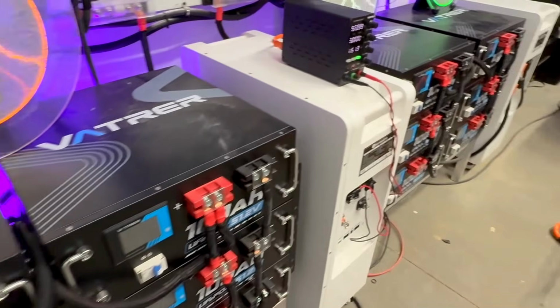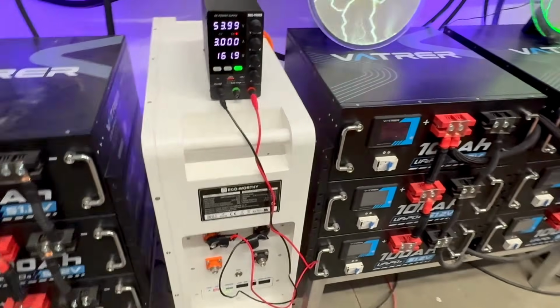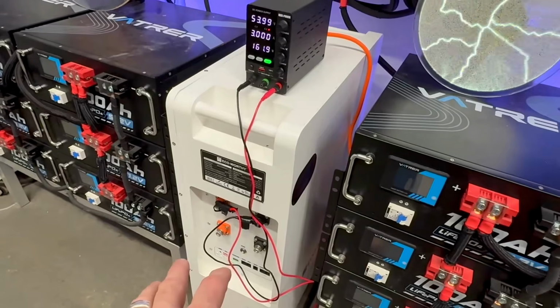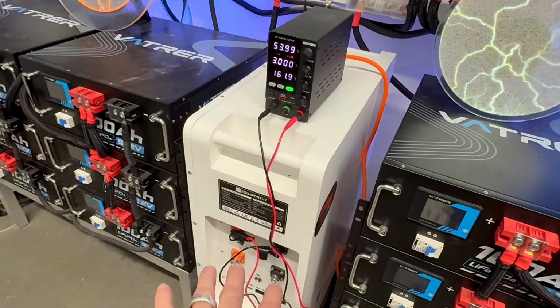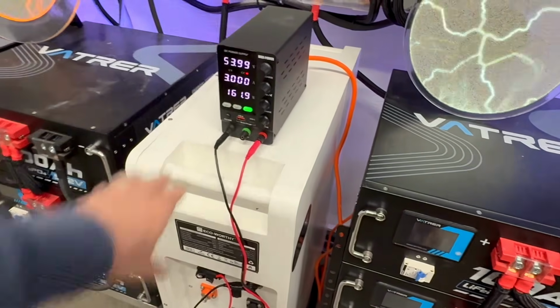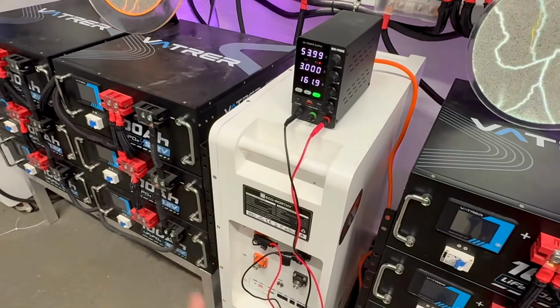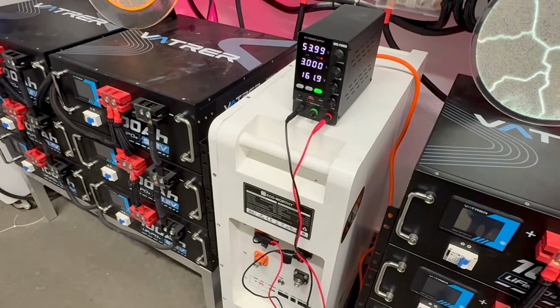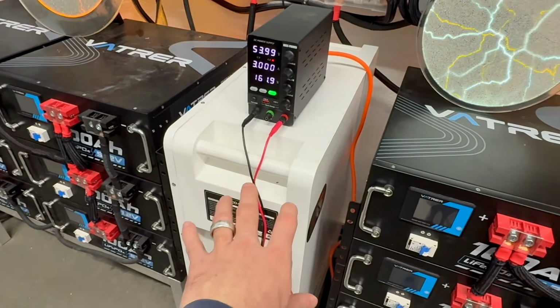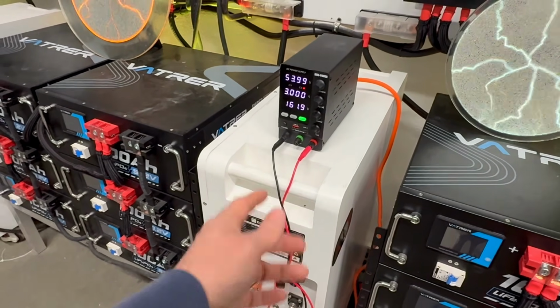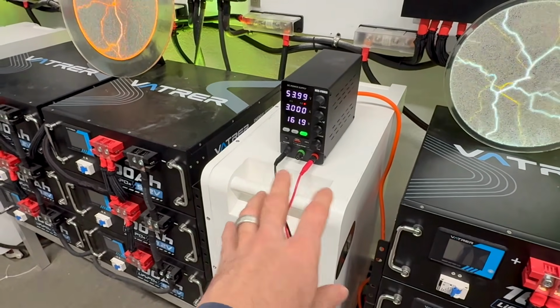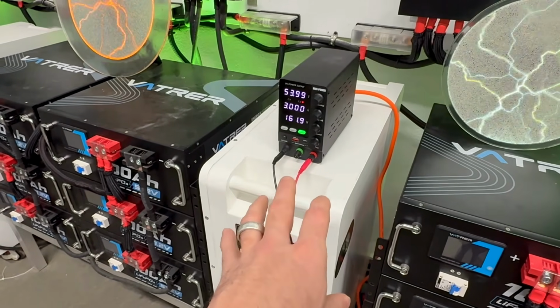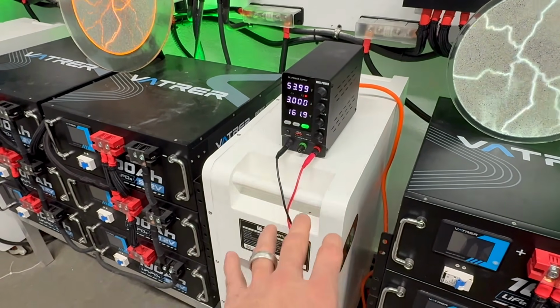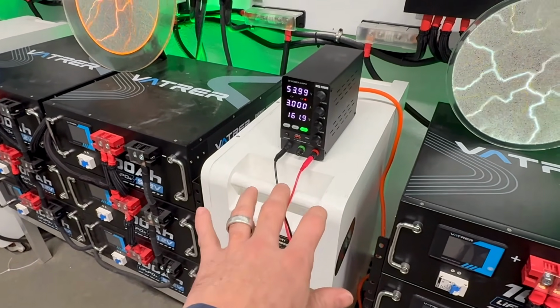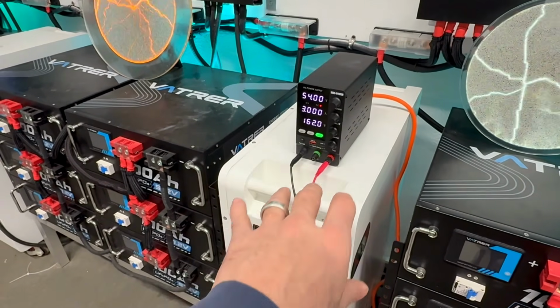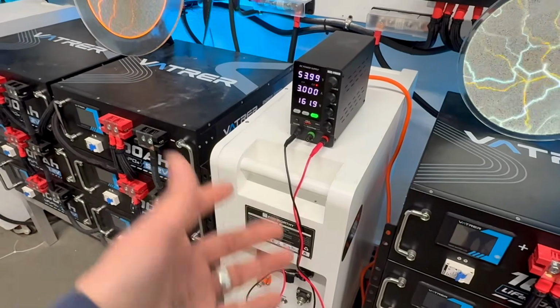If all of your cells are welded together, like in this EcoWorthy, what you want to do is maybe bring the charge down to about 80%, connect a small charger, and slowly charge it up to 100%. Especially with a passive balancer like the one inside this EcoWorthy, if you charge at a slow rate, once it gets around 3.45 volts per cell, that top cell will start bleeding off through the resistors in the BMS. So charging very slowly to get it up to 100% that initial time will help balance out the cells.